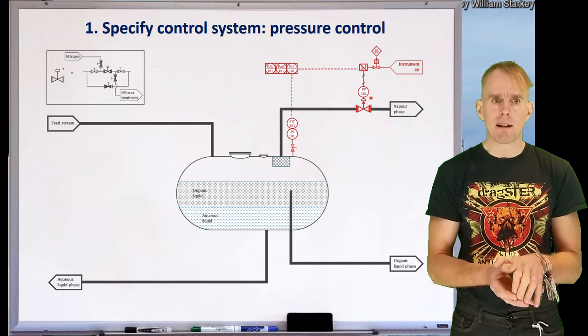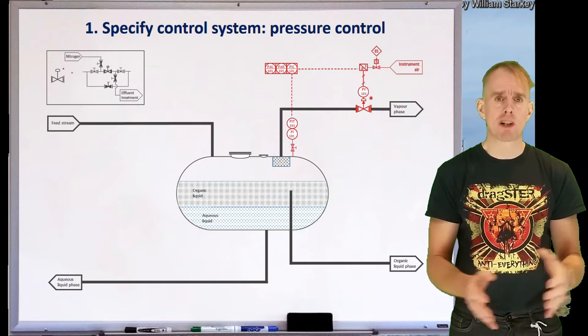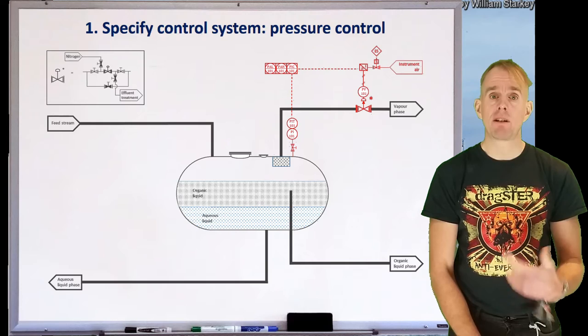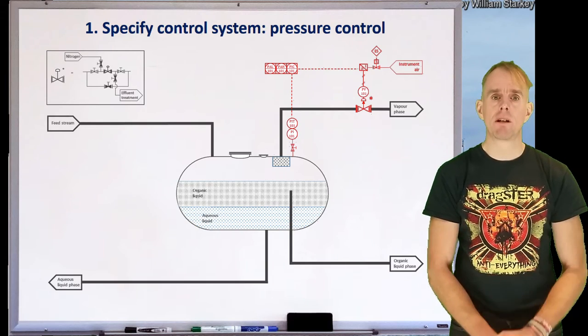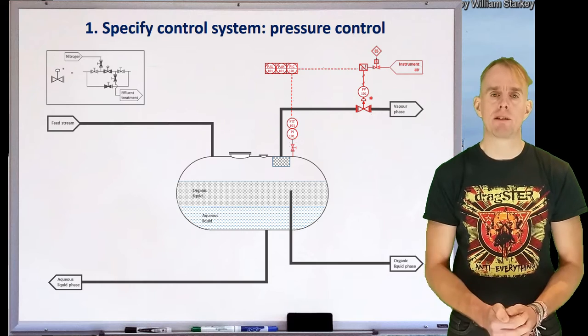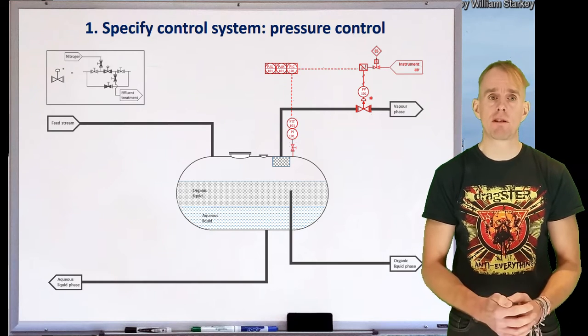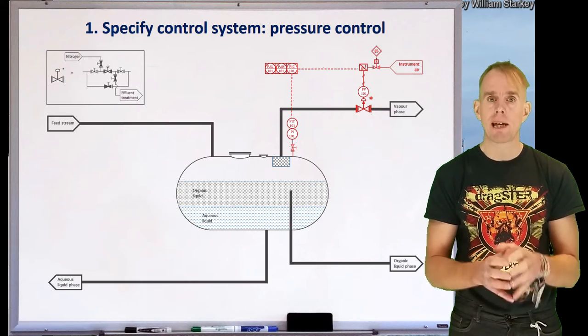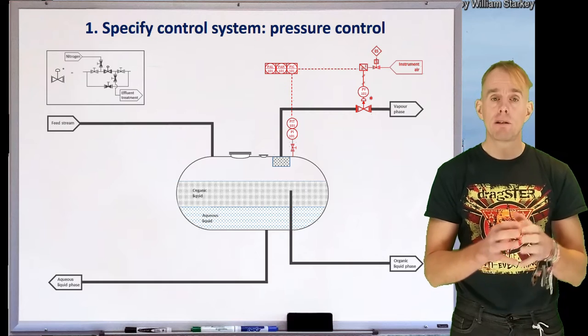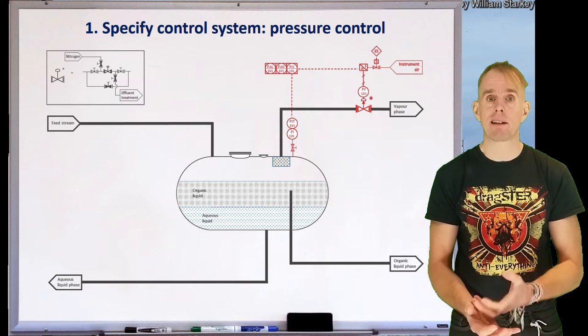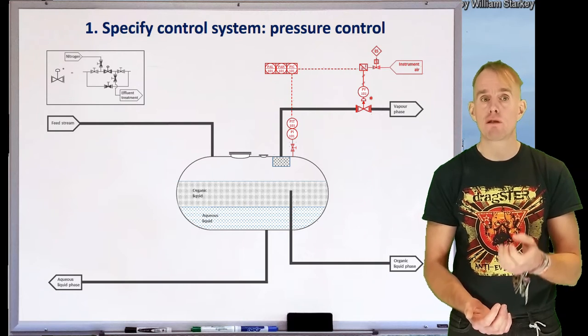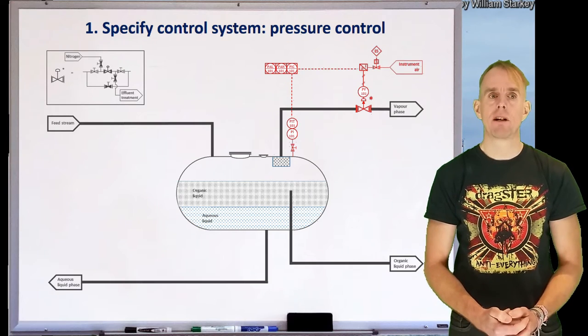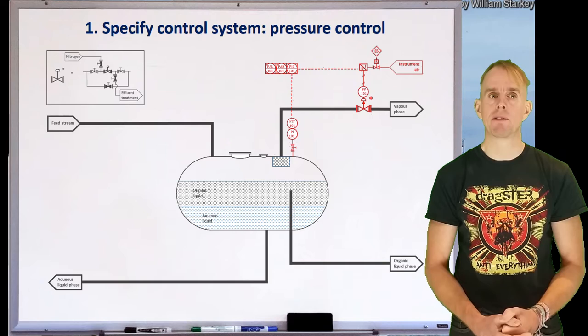The pressure indicator — the PI — will measure our pressure range, let's say 0 to 10 bar, and produce an electrical signal. That signal needs to be conditioned to fall within a control standard. Using the current standard of 4 to 20 milliamps, that conditioning is the function of the PIT, the pressure indicator transmitter. This produces an electrical signal, shown by the dashed line connecting clusters of instruments together.